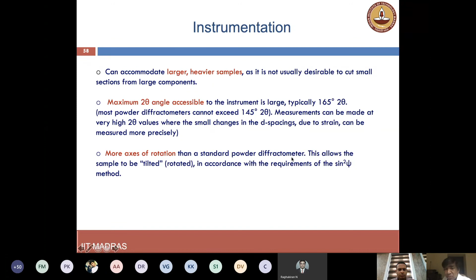You may be wondering, I have not talked about sample preparation. Mechanical methods such as grinding, machining, and so on should not be done. For example, if somebody comes with a sample and asks you to measure a stress, you cannot do any surface preparation. You should not do that because you will create an artifact. If you have a painted material, it's okay, because so long as the X-rays can penetrate through the paint, it is still okay. If the paint is too thick and the intensities come down, then possibly we have to think of removing the paint without any destructive methodology.